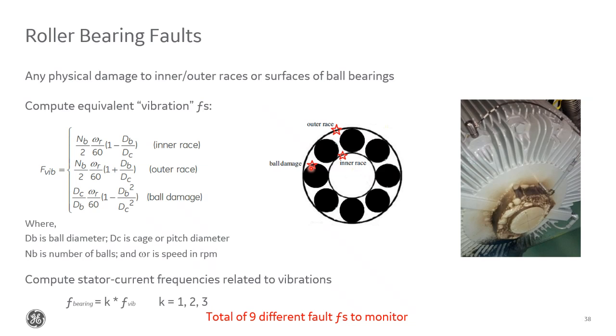Sleeve bearings are different, and currently we don't monitor those. So if you only have sleeve bearings, you can still use ESA, but you'd need to disable this bearing part of it. So basically, a bearing failure causes a vibration, and this vibration is what shows up in the stator current signal. The way that we calculate the bearing fault frequencies is as we see here. I won't go into great depth on the science behind these calculations. If you're interested, we can definitely provide you with more info.